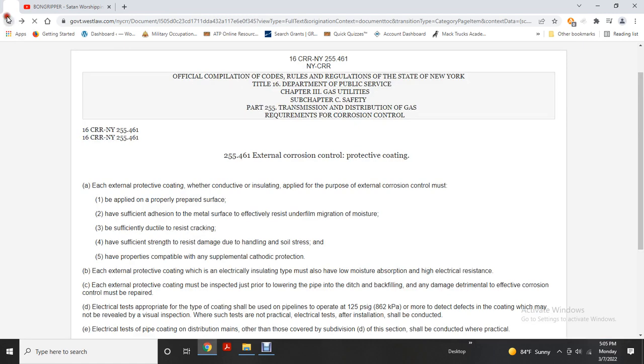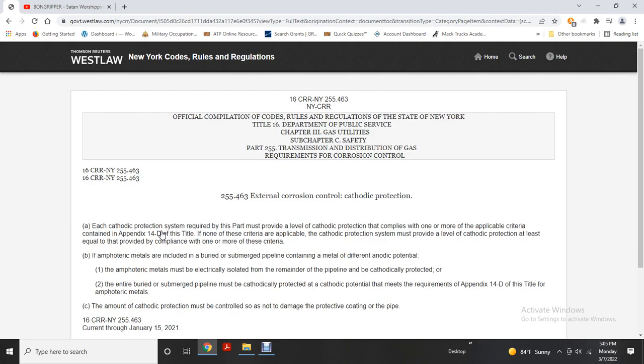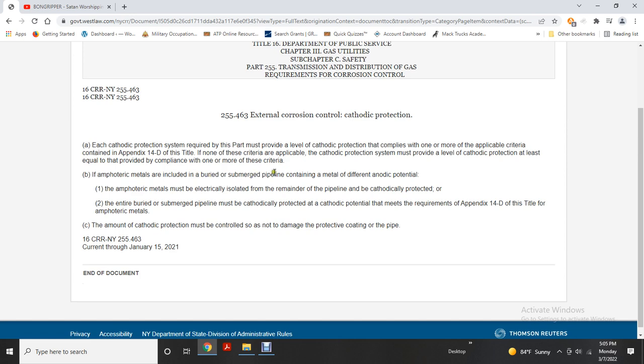Cathodic protection: each cathodic protection system required by this part must provide a level of cathodic protection complying with one or more of the applicable criteria contained in Appendix 14D. If none of the criteria is applicable, the system must provide at least an equivalent level of protection. Amphoteric metals included in buried or submerged pipelines with different anodic potential must be electrically isolated from the remainder of the cathodically protected pipeline. The cathodic protection must not cause damage to the protective coating of the piping.